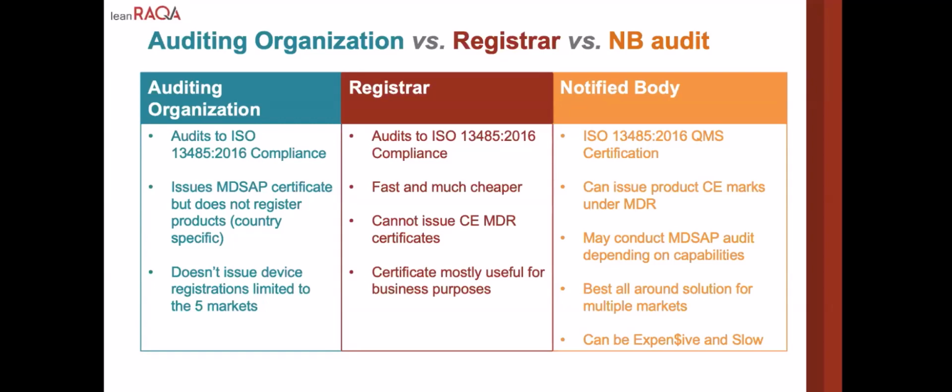A registrar also audits to 13485 for compliance. It's much faster and cheaper than either an audit organization or a notified body. They cannot issue an MDSAP certificate or a CE mark or an MDR quality system certificate. This certificate is very limited in its utility. It's mostly useful for business purposes. Maybe if your customers want one, or you want to advertise it for marketing purposes.